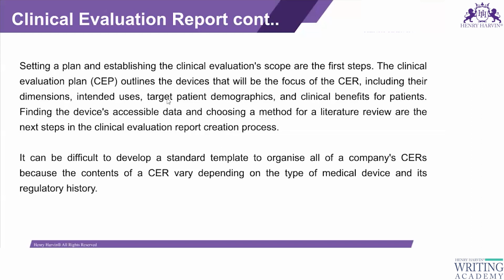So the clinical evaluation plan outlines the devices that will be the focus of the clinical evaluation report, what the dimensions are, and what software is used. It also covers for what purpose the medical device is being used, in what target population it is being used, and what the clinical benefits of the medical device are. The clinical evaluation plan is made on the basis of all that information. Finding the device's accessible data and choosing a method for a literature review are the next steps in the clinical evaluation report creation process.